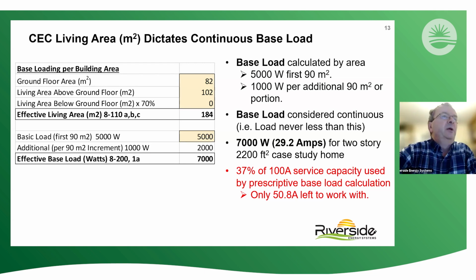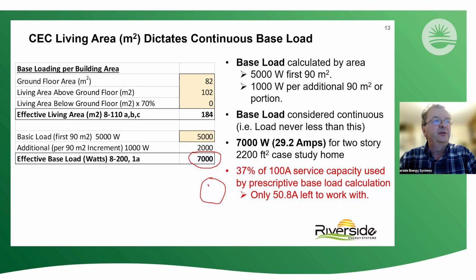That constraint, on top of continuous base loads, or basic load, as it's also called, is founded on strictly the living area of the building. So in the case of this Kamloops case study house that we're looking at, there's 184 square meters of effective living area. And based on that, we have to apply these stringent rules of thumb, and we wind up with literally a 7,000 watt assumption of basic load, which means that we've already taken up 37% of our 100 amp service, and we've only got 50.8 amps to work with. So that's a pretty big bite. Just applying a rule of thumb.